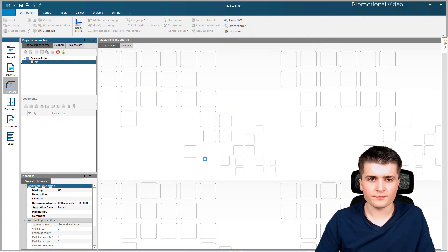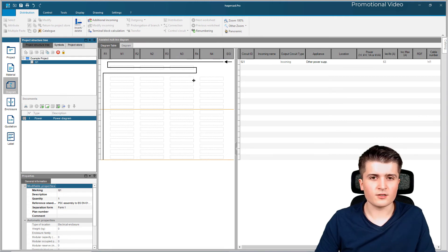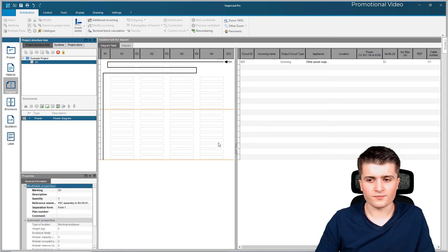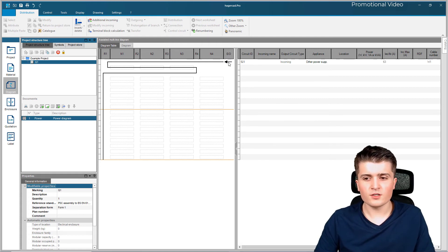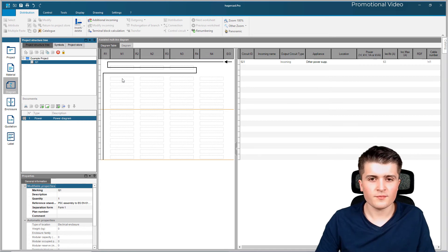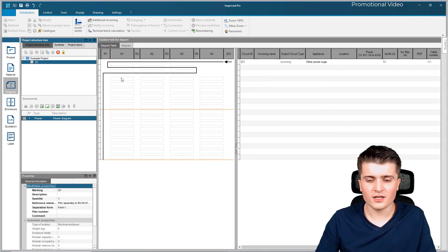And we are prompted to this diagram table - and this is where the magic happens. In this window we will place the devices that we have within our switching board, and based on this HagerCAD will draw the diagram by itself. Here by this arrow you can see the incoming that we just specified, and this black line is the current path with the current loop where we can place devices - three devices in total. Then down below we have multiple rows where we can place for example circuit breakers or RCD devices, and when we place them down here we have the circuit that we create.